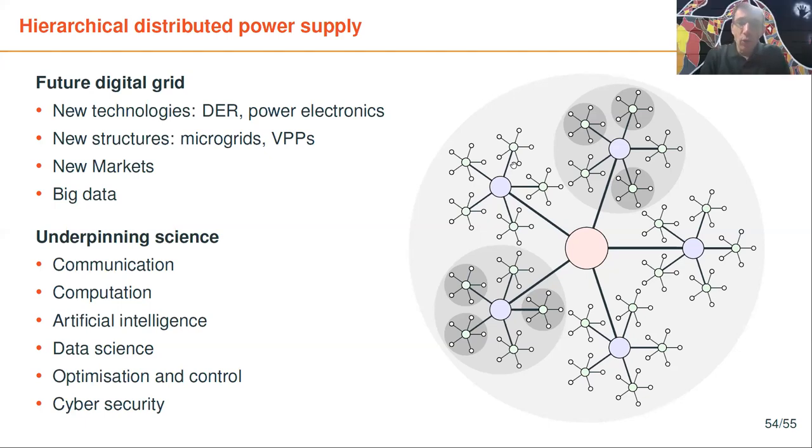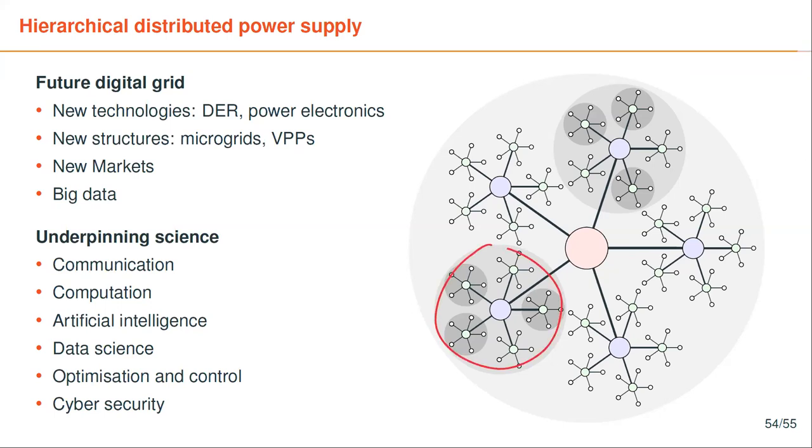Yeah. So low voltage networks in Australia are around a few hundred customers. Typically, low voltage networks in Europe and Australia are a bit different to what you have in North America. The number of customers in one low voltage network can be a few hundred, for example, between 0.5 megawatts and maybe 1.5 megawatts. But a medium voltage network can be up to 50 megawatts, so probably up to several tens of low voltage networks, several thousands of customers.